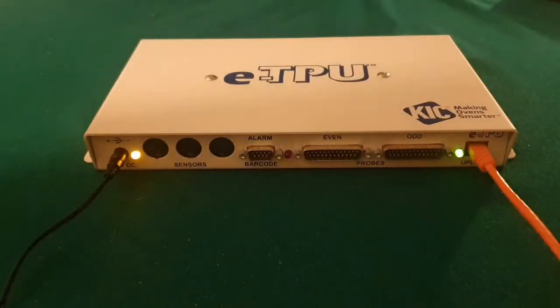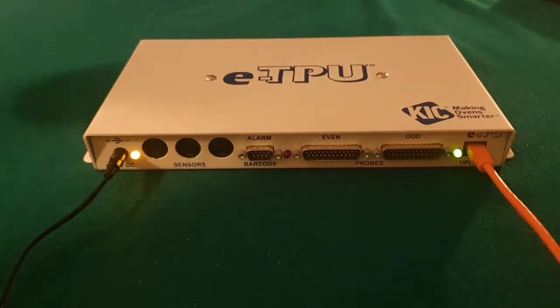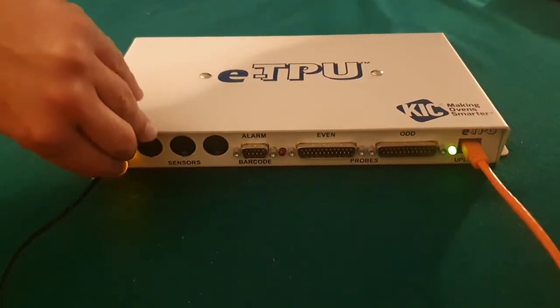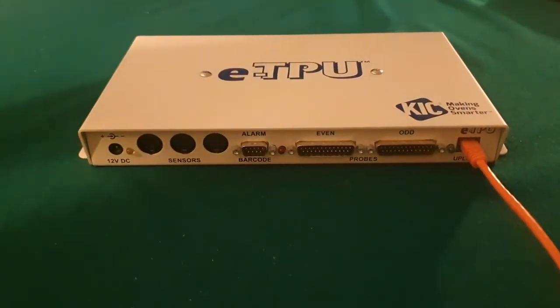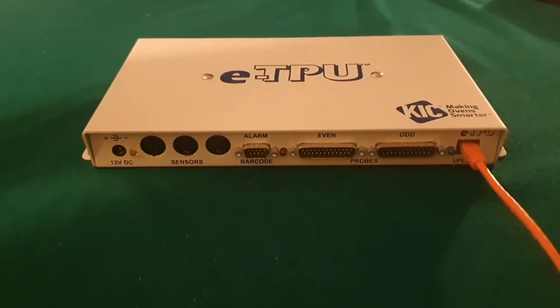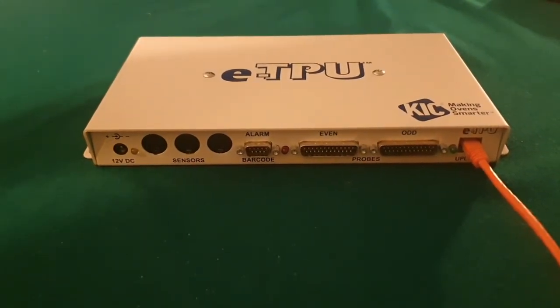Now that you have verified that all the proper hardware and software is available, we will show you an example of how to properly connect and set up the temperature calibrator. Please remember always to unplug the power from the eTPU, as shown in the video, before plugging or unplugging any cable. This will prevent damaging the unit.